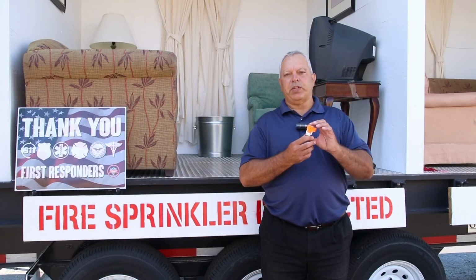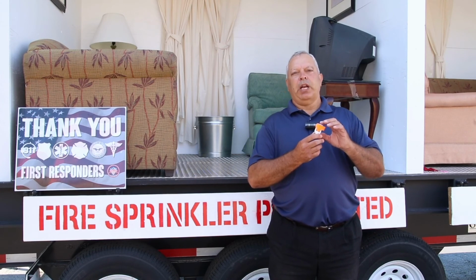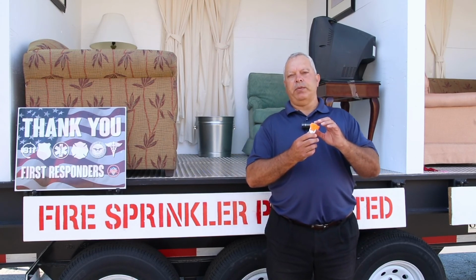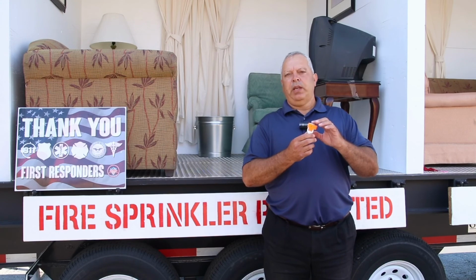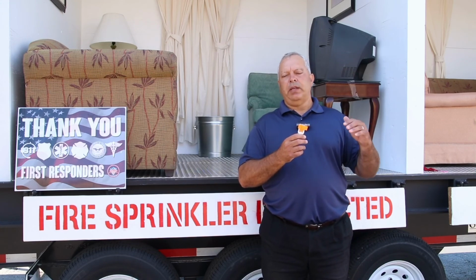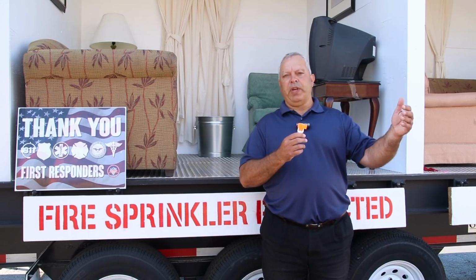Today we are using a residential quick response fire sprinkler. It operates 4 times faster than a standard sprinkler of the same temperature rating. It also shoots the water out horizontally, cooling the hot air and gases, preventing flashover.